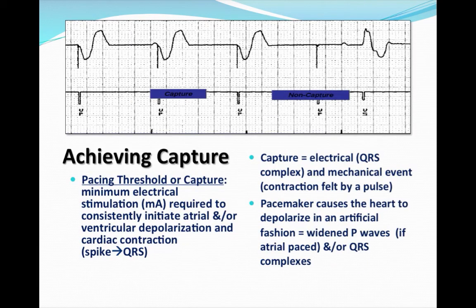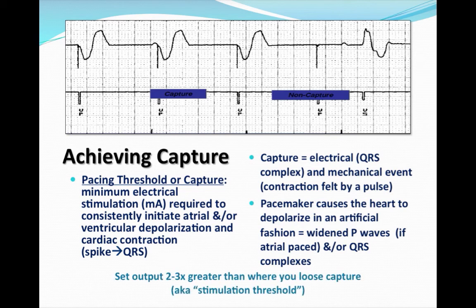Once the pacemaker is in the heart, we want 100% capture — a pacer spike followed by a wide QRS with ventricular pacing. In the picture above, you can see a pacer spike and wide QRS for three beats, then a pacer spike with no wide complex. That means the output or milliamps is not high enough to achieve capture 100% of the time. The output should be set two to three times greater than where we lose capture — this is called the stimulation threshold.